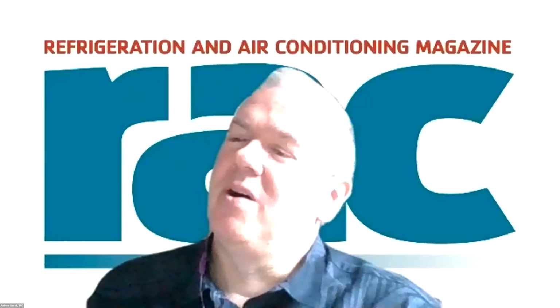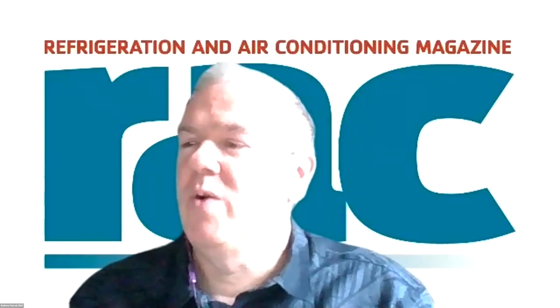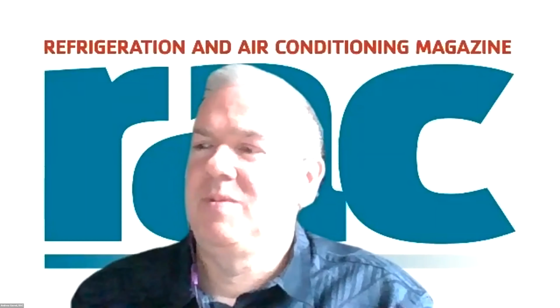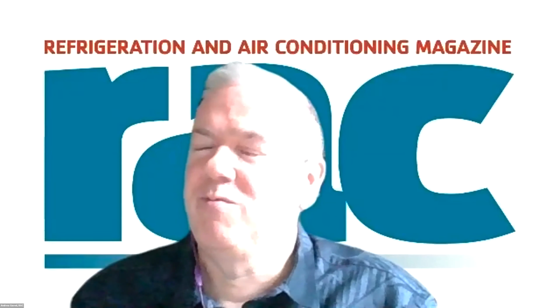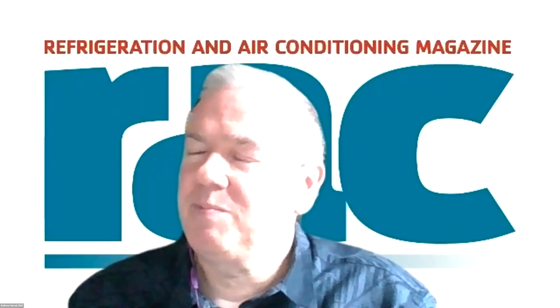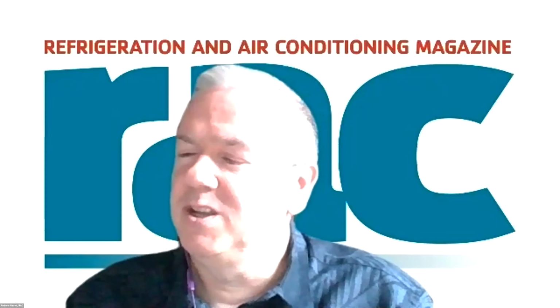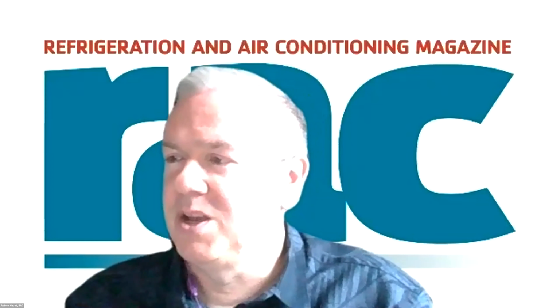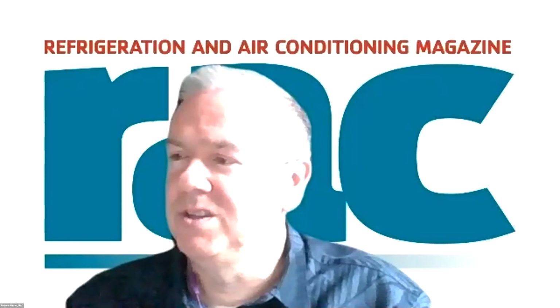Right, in the last 2 minutes then, Brian, give us a real quick overview of where you see development going, because we can't avoid the fact you're sitting in front of one of your Mistral systems. How's the virtuous circle between those kind of ducted systems and new refrigerants developing? So we already have a new installation using an HFO standard on the Mistral display, in one of our brand new stores. We hope to potentially get other innovation into that store as well, but we could take it as far as using A2L packs on Mistral air handling units.